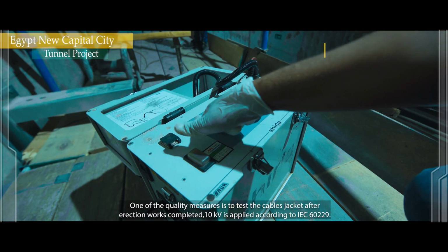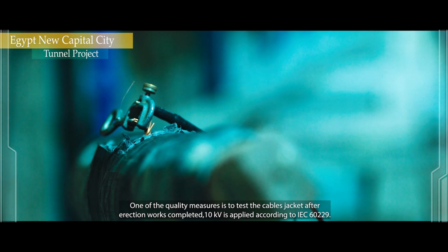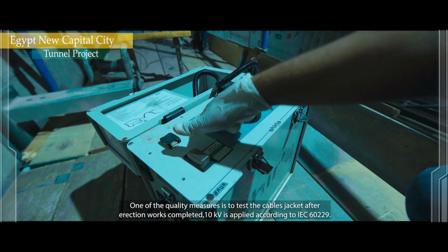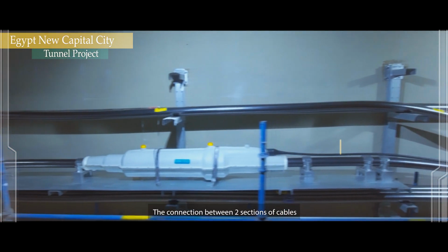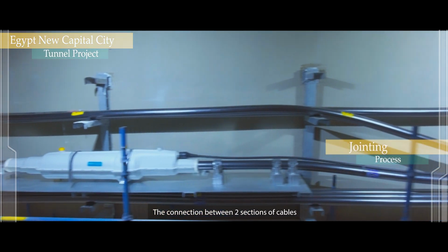One of the quality measures is to test the cable's jacket after erection works are completed. 10 kilovolts is applied according to IEC 60229, for the connection between two sections of cables.